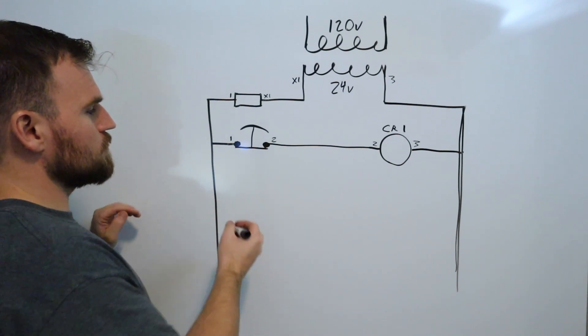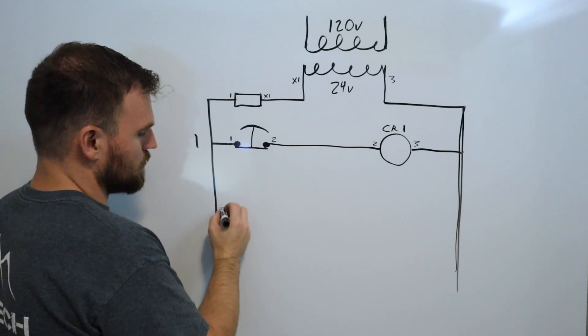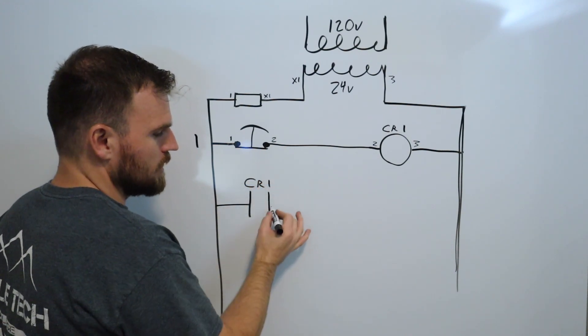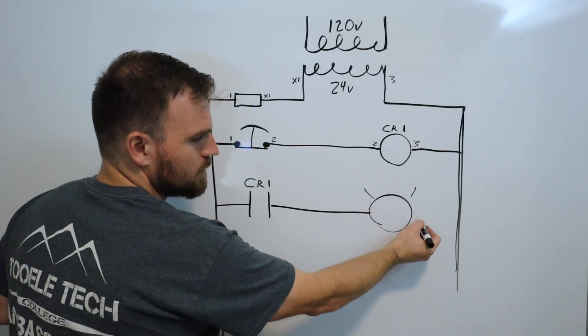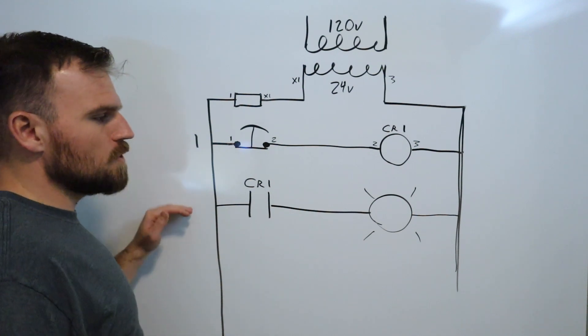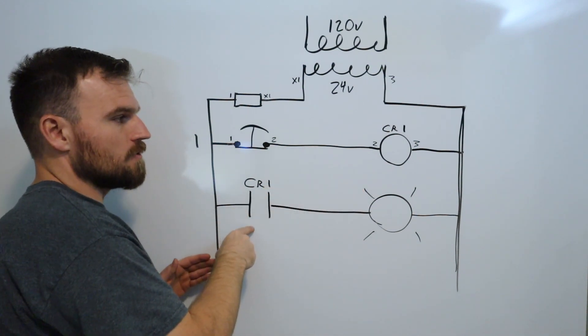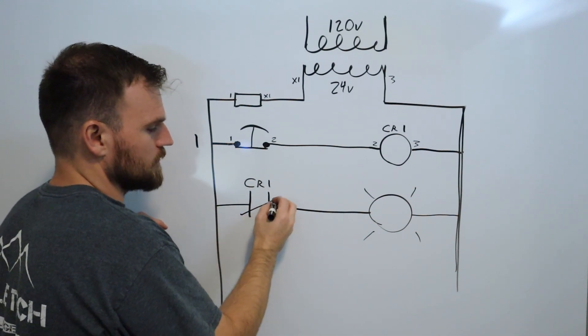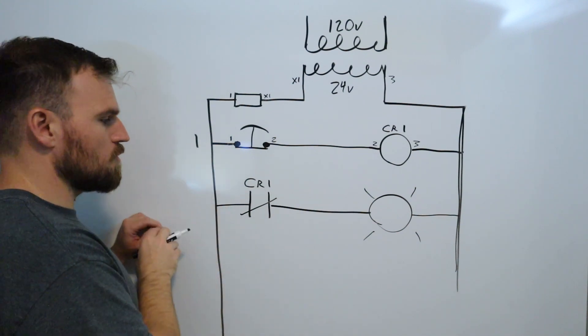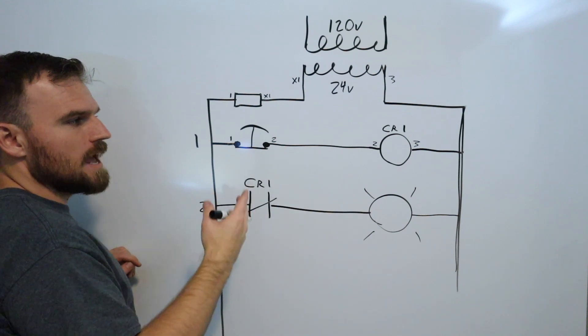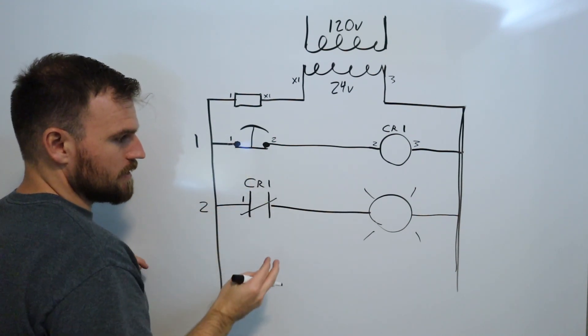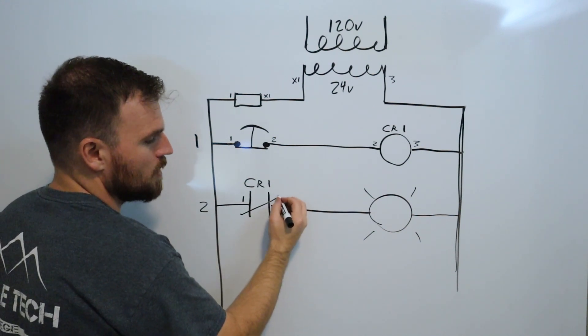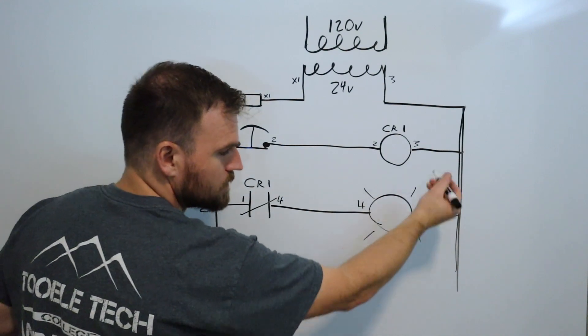Rung one is always labeled rung one. Rung two can include a contact from CR1 - make sure it's labeled CR1 - which turns on a light. So rung one controls rung two through the relay. In rung one, wire one enters, becomes wire two through the switch, goes through CR1 coil, and returns as wire three. In rung two, wire one comes in, passes through the CR1 contact as wire four, goes to the light, and returns as wire three.